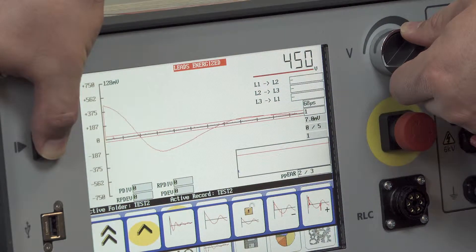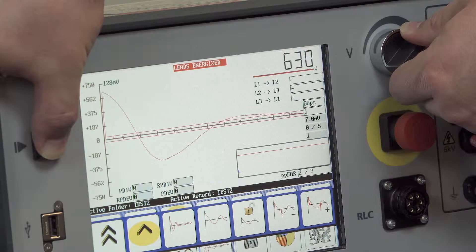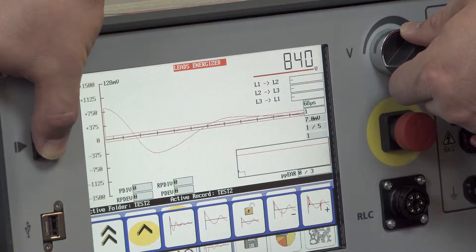We simply ramp to test voltage. Now I'm going to do a surge test to 2,000 volts as this is a 460 volt motor.